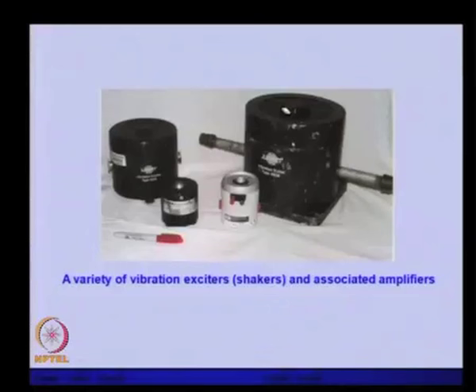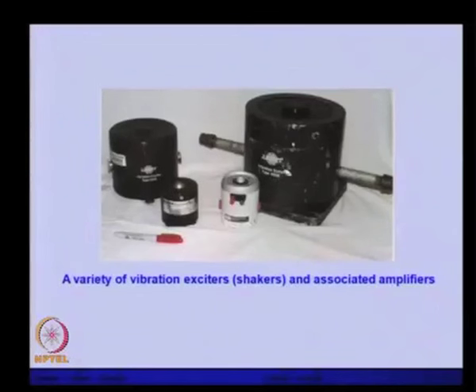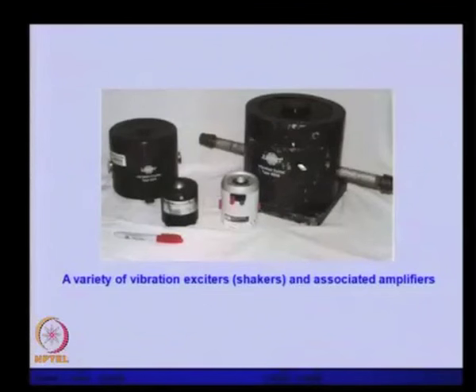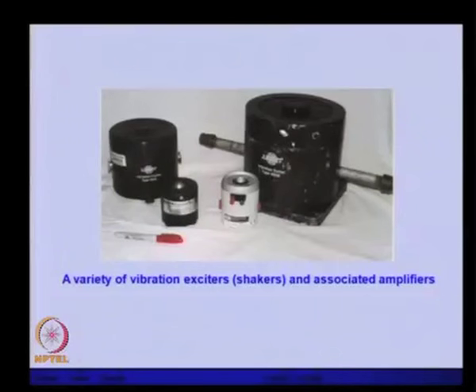Another instrument is the vibration exciter or shaker. Various shapes and sizes of shakers are available depending on what kind of machinery we want to excite. With the shaker, we can excite the machinery externally and choose the frequency and amplitude of excitation, or even the type of excitation force — sinusoidal, two-frequency, multiple-frequency, or random signal. We can then measure the corresponding change in vibration to find the condition of the machine.